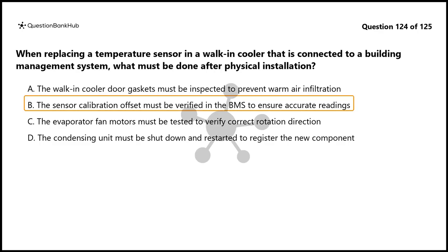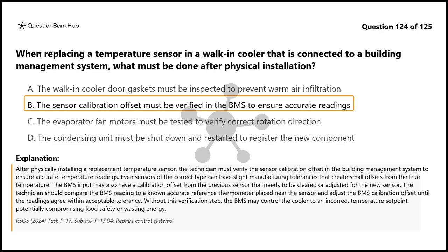The correct answer is B. After physically installing a replacement temperature sensor, the technician must verify the sensor calibration offset in the building management system to ensure accurate temperature readings. Even sensors of the correct type can have slight manufacturing tolerances that create small offsets from the true temperature.